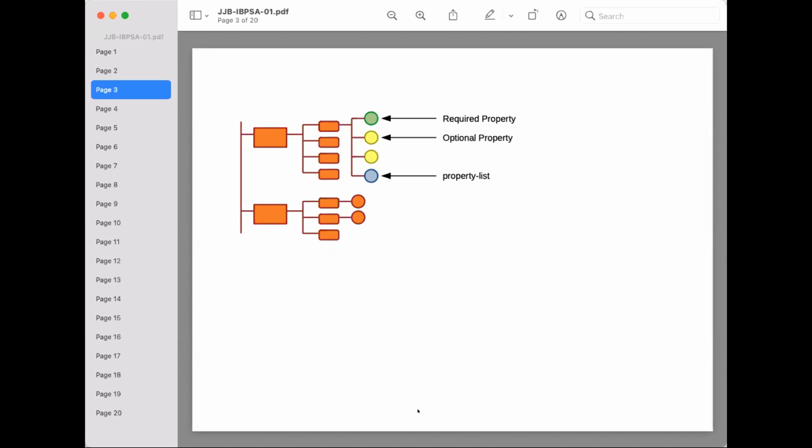To assist with integration, BACnet objects have standardized metadata properties like this special one called the property list property that can reflect what is being implemented in a device. So you can pick a device, plug it into the network, and using standard sets of services, find out what kinds of capabilities that device provides, what kinds of objects, and what their names are and how they're related in some loose sense.